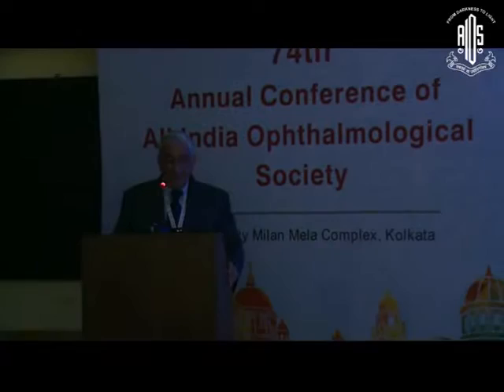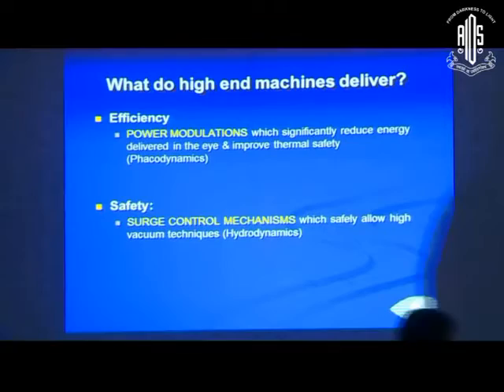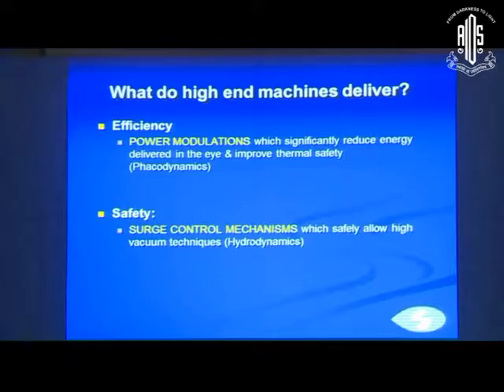After covering the basics about power and fluidics, we will now go to newer power modulations and high-end fluidics present in the new machines. Higher-end machines offer efficiency and safety. Power modulations significantly reduce energy delivered in the eye and improve thermal safety — this is called phaco-dynamics — and surge control mechanisms allow surgery at high vacuum, which is called hydrodynamics.